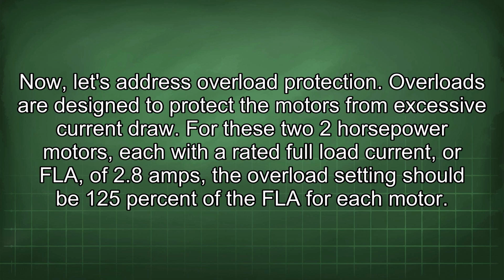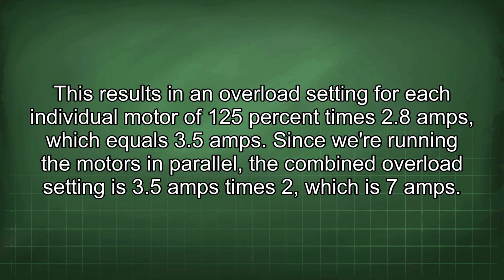For these two 2 horsepower motors, each with a rated full load current, or FLA, of 2.8 amps, the overload setting should be 125% of the FLA for each motor. This results in an overload setting for each individual motor of 125% times 2.8 amps, which equals 3.5 amps. Since we're running the motors in parallel, the combined overload setting is 3.5 amps times 2, which is 7 amps.